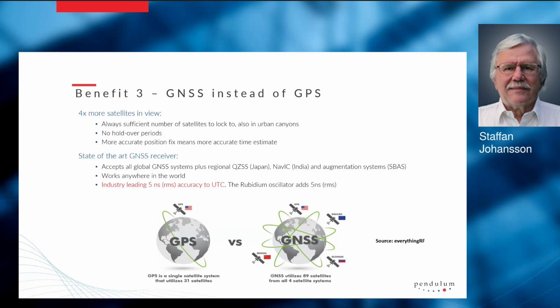Using GNSS instead of GPS, as is commonly found in legacy frequency standards. Even if GNSS receivers are nowadays the most used in new frequency standards, there are still very many legacy frequency standards around that use GPS only. Basically, you have 4 times more satellites in view because you have 4 times the number of satellite constellations, not just GPS, but also Galileo, the European, Beidou, the Chinese, and GLONASS, the Russian. It means you have more opportunities to lock to the satellites. You will eliminate the periods where you don't have any lock and you enter holdover.